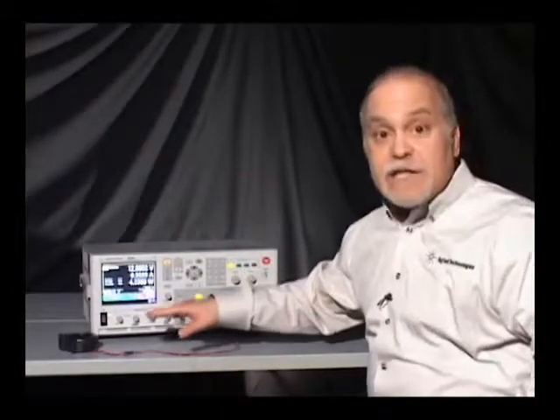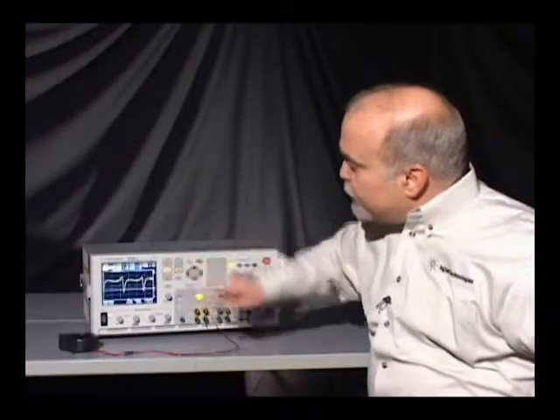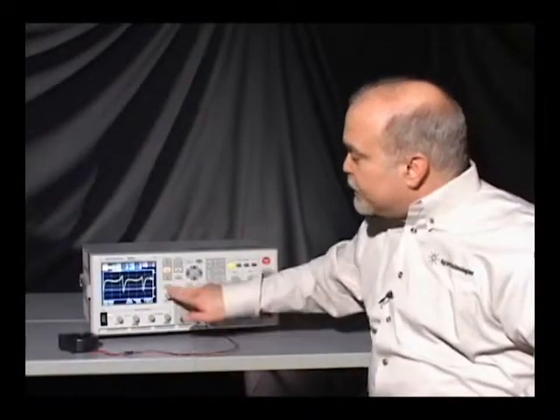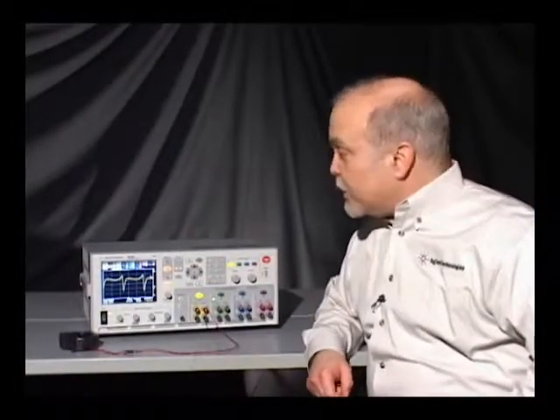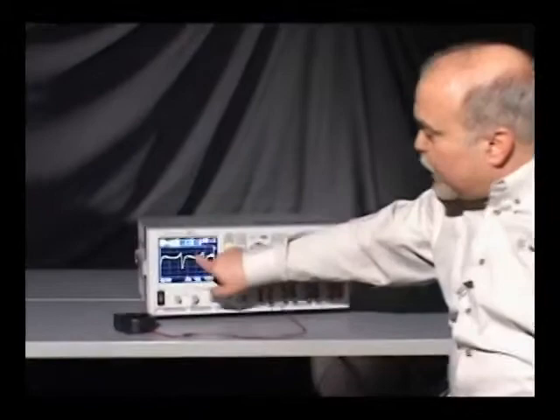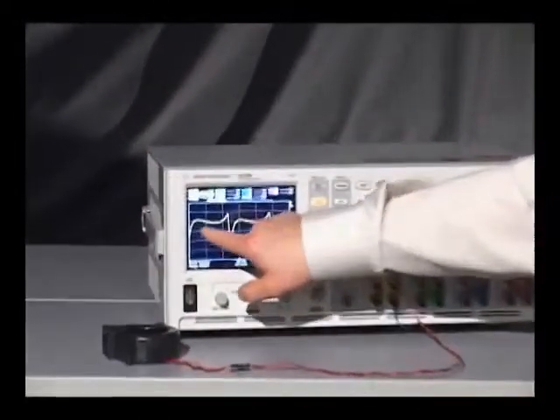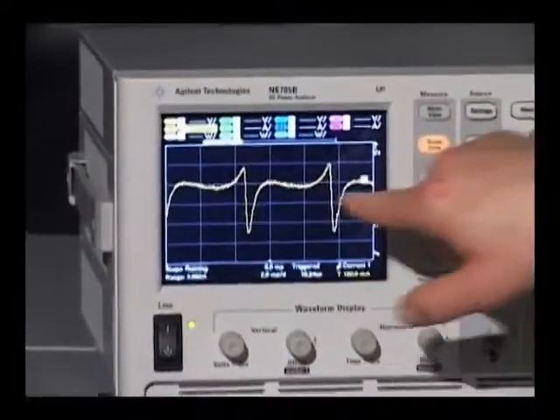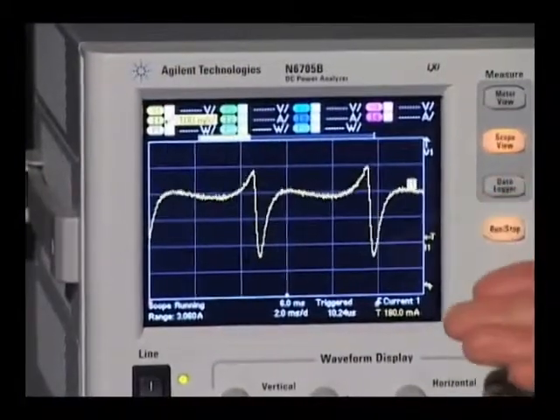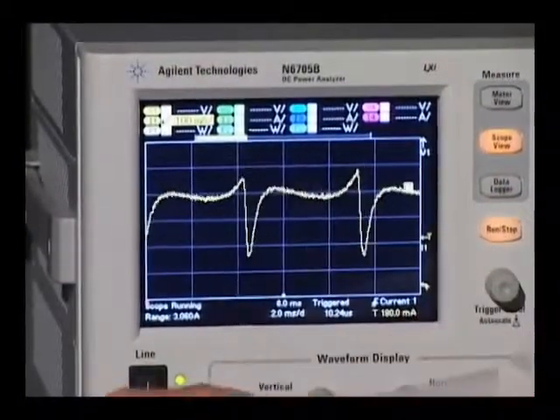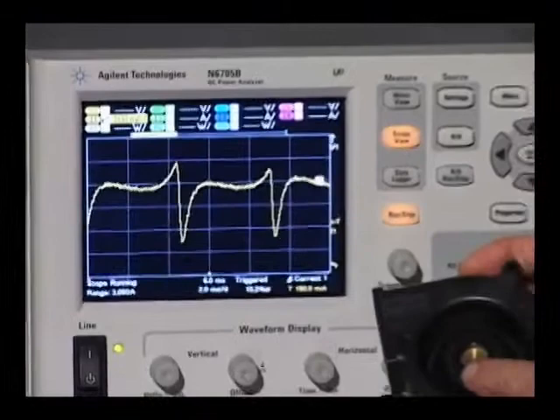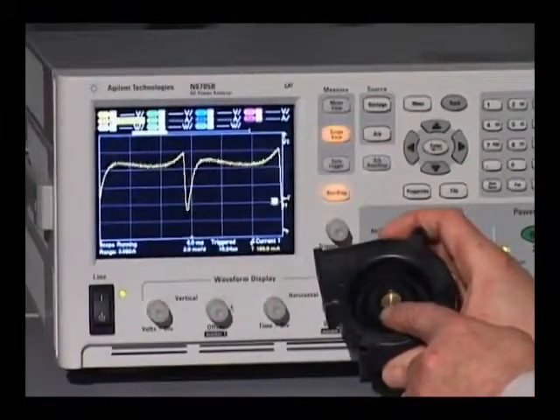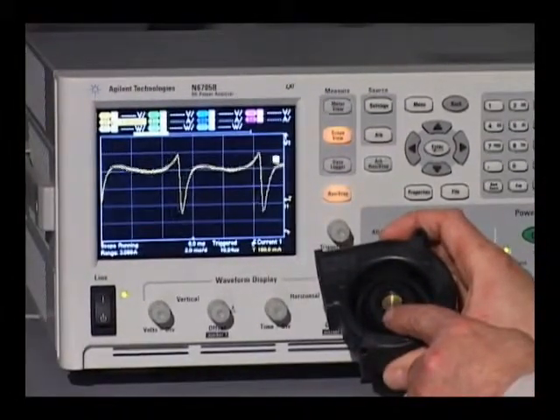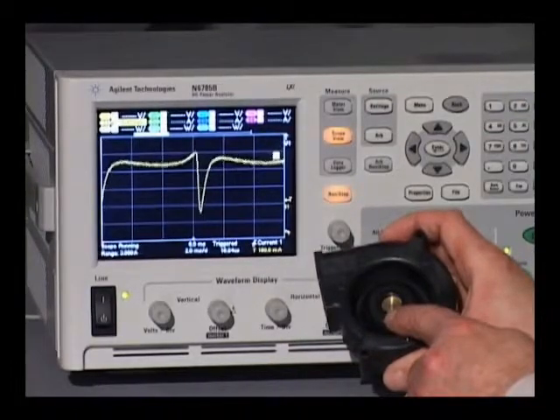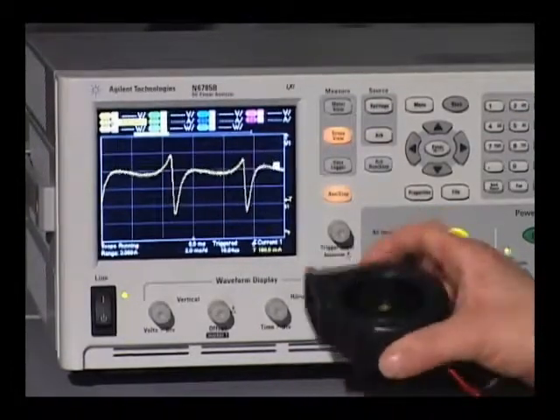So now to access the oscilloscope function, I push the scope view button, and now what you can see is the scope trace of the fan current. So what we're looking at here is current versus time on the fan, and you can actually see that it's not at all DC, but it's actually a current waveform. Now this is a live waveform, a live measurement. As I take the fan and slow it down with my finger, you can see the waveform changes shape. As I slow down the fan rotation, the period of that waveform changes.